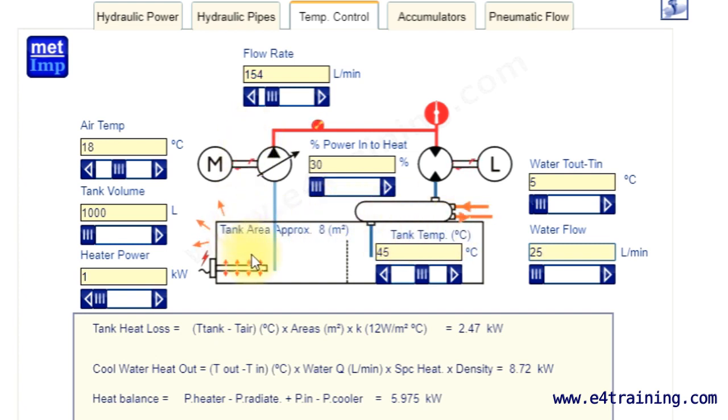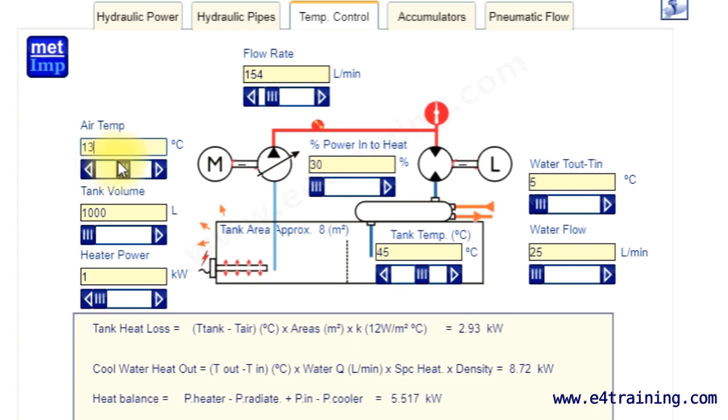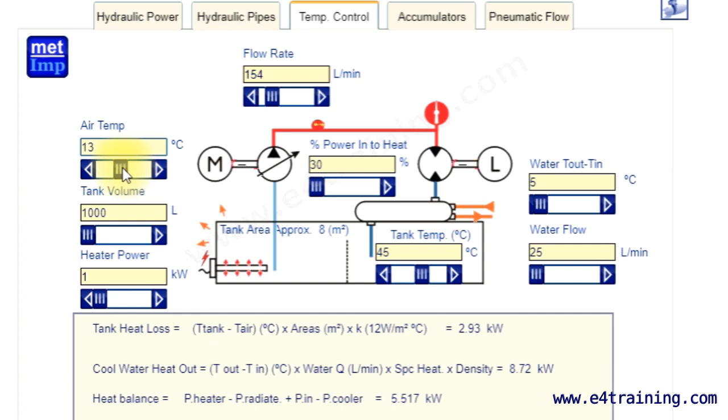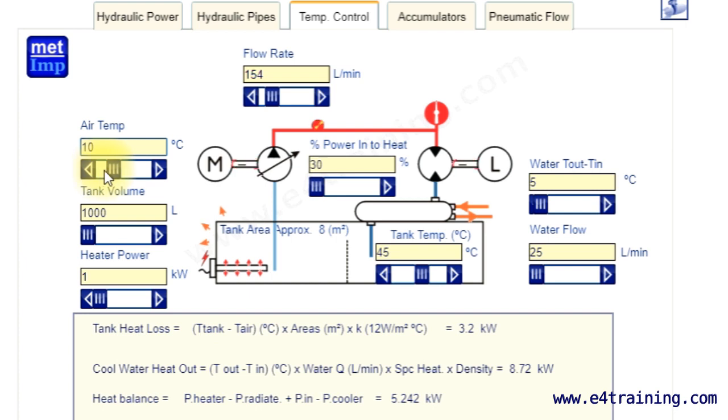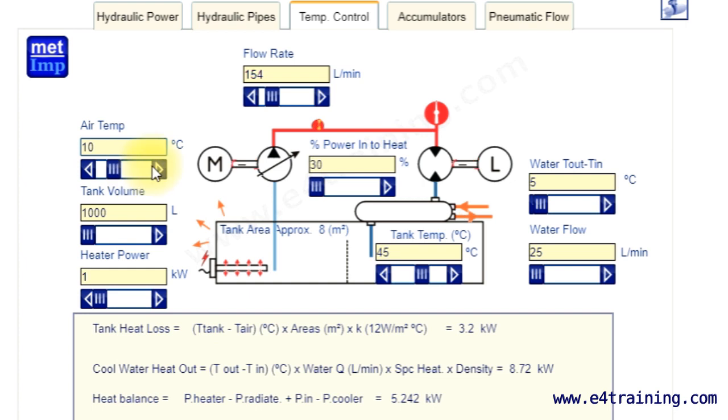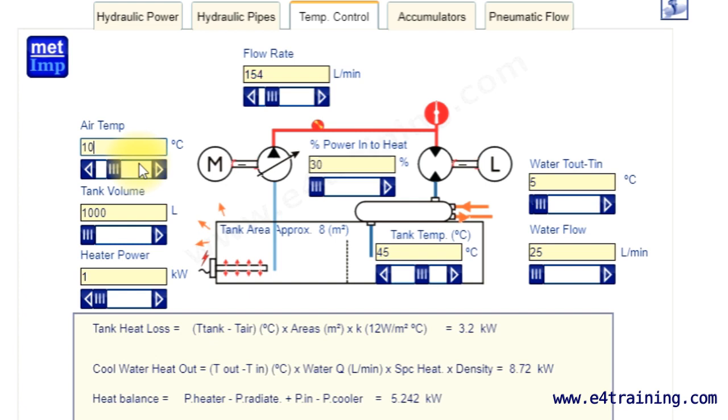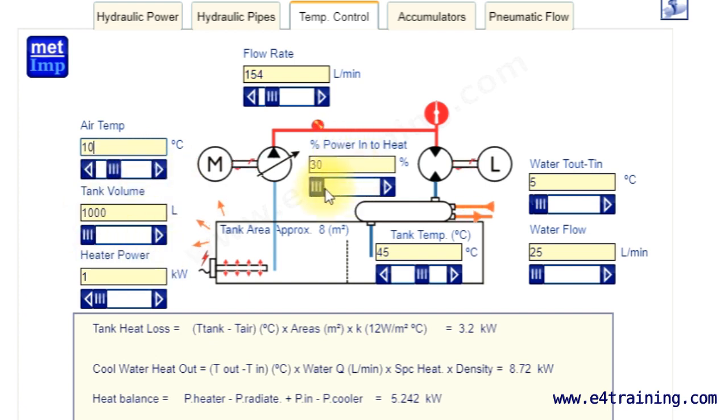So you can just experiment here. You can put in your temperatures, because this is one thing, it's fine doing one calculation in a mathcad sheet, but really temperatures change. So you need to check what's happening under different conditions, even going to negative. One of the only problems I've had was when someone was running a reservoir outside at minus five and the fluid got too thick. You can quickly check here across the range of situations and see what you need to do heating-wise and where you can leave units.